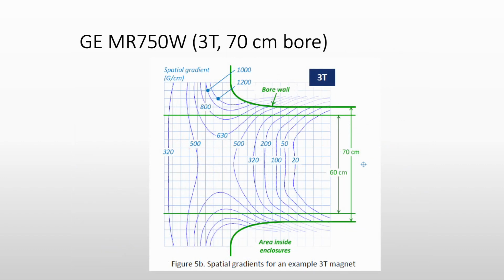Here is a spatial gradient map for a 3T GE system. You can see the bore wall here with the large green line, and the maximum spatial gradient of 1200 Gauss per centimeter noted on the outside of the bore. But you should also note that the patient typically will travel between the two green lines noted here, so the patient will be traveling through spatial gradient areas of 320, 500, 630, 500, and then down to 0 gradient as they move into the bore. So even though the manufacturer specifies that 1200 may be the maximum spatial gradient for this system, you need to assess whether the patient will exceed the maximum spatial gradients for their specific device of potentially up to 630 Gauss per centimeter.